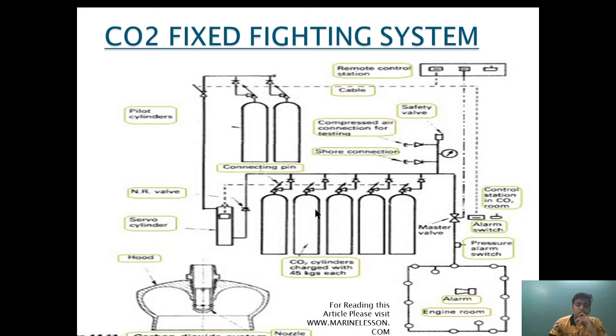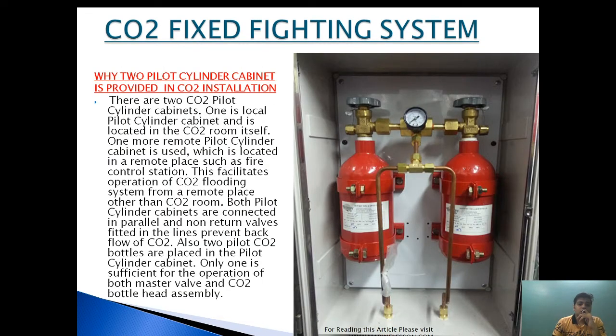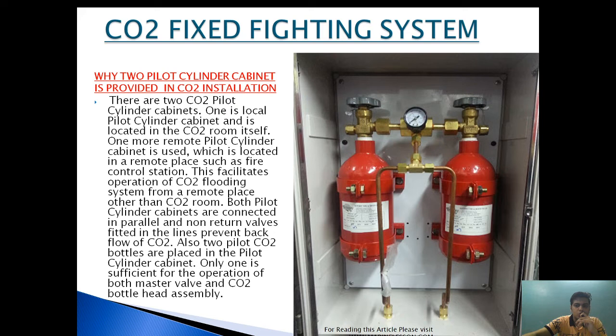If one pilot cylinder bottle is punctured, that is enough to move the servo cylinder and pull the connecting pin wire downward, ensuring puncturing of the CO2 cylinders in bulk. There are two CO2 pilot cylinder cabinets: one is the local pilot cylinder cabinet and the other is the main remote pilot cylinder cabinet. Basically four pilot bottles are provided — two in the remote control area (fire control station) and two in the local control area (CO2 room). The preference is to actuate from the CO2 room if access is available.